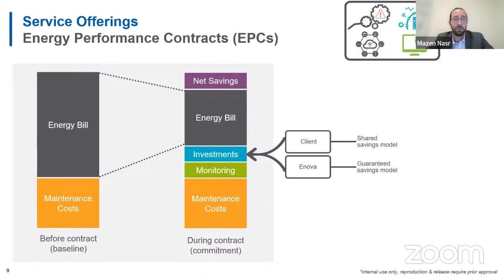But now the digital boosters have stepped in, and we've greatly enhanced the performance of our EPCs by, one, identifying faults and potential improvements within minutes of their occurrence. As we spoke earlier, every 5 minutes we're doing automatic fault detection, and thanks to digital twins, machine learning, and continuous commissioning, we're able to uncover potential for a lot more savings than what we previously identified during the initial stages of the study.